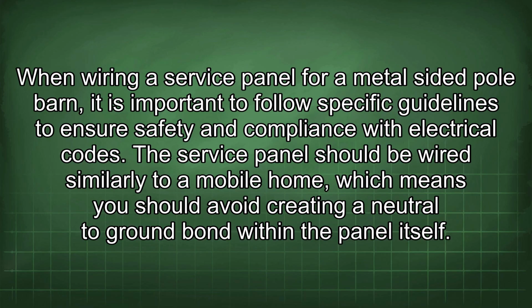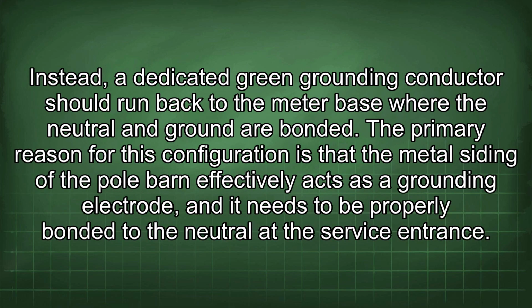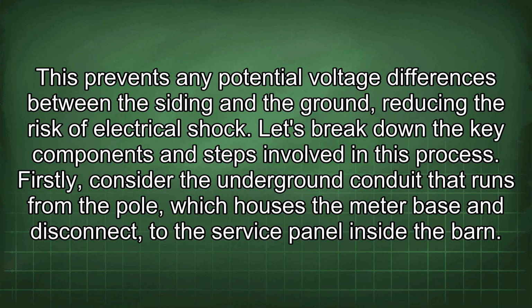When wiring a service panel for a metal-sided pole barn, it is important to follow specific guidelines to ensure safety and compliance with electrical codes. A service panel should be wired similarly to a mobile home, which means you should avoid creating a neutral to ground bond within the panel itself. Instead, a dedicated green grounding conductor should run back to the meter base where the neutral and ground are bonded. The primary reason for this configuration is that the metal siding of the pole barn effectively acts as a grounding electrode, and it needs to be properly bonded to the neutral at the service entrance. This prevents any potential voltage differences between the siding and the ground, reducing the risk of electrical shock.